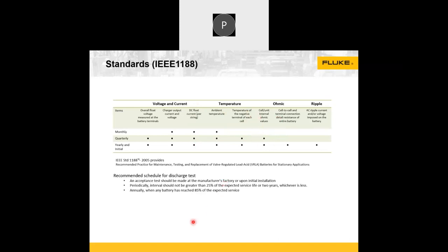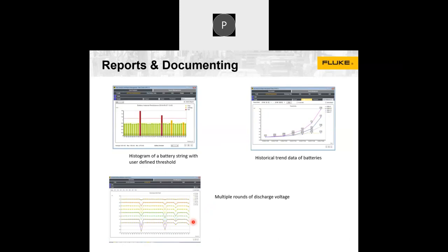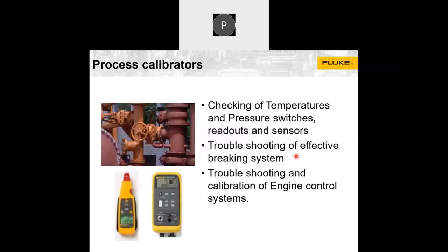Interestingly, when you do all these tests, how do you verify - today you are verifying, after 2 weeks or after a month you are verifying, but how do you keep those records? That we are sorting out by giving you an internal memory, and it can store data for a string of batteries for months together, or you can download it to a PC and compare it on a timely basis. That means you can see whether your batteries are deteriorating or improving or maintaining the same internal condition. That way you can be ensured these batteries are not dying without your permission or knowledge.